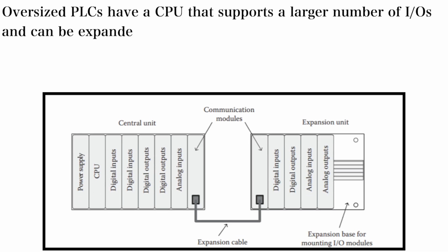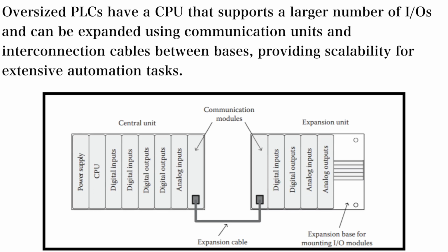But it has to be ensured the PLC fully corresponds to the application requirement. So mainly we can select from various input output and special purpose modules. Next, the oversized PLCs. The oversized programmable logic controllers have a CPU, the central processing unit, that supports a large number of input outputs and can be expanded using the communication units and interconnection cables available between various bases, and it provides scalability for an extensive automation task.